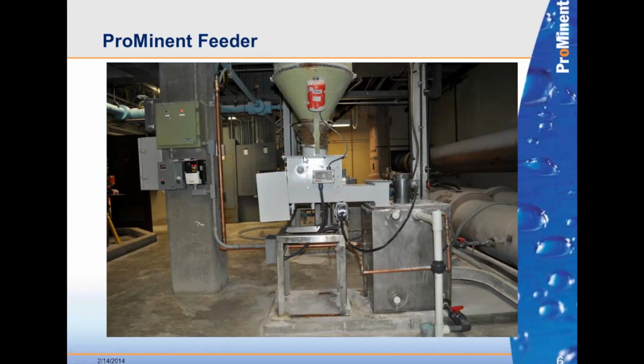We talked to them before they did it and told them that we would like to have a bigger opening. If it didn't work well, or if there's a lot of arch buildup or anything like that, then eventually we might need to go in and replace from here down. But they knew that going in. In the end, it's actually working fine. There's another reason why they think it's working fine, but we were able to reuse the existing vibrator in the butterfly valve here.